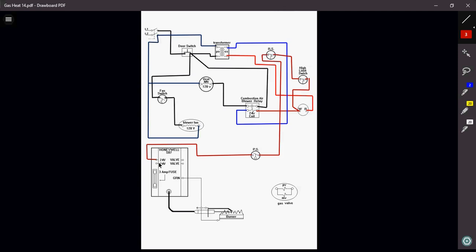Okay? Because where does that call for heat come from? That call for heat comes from the thermostat. My thermostat is right here. So once that switch closes between R and W, I'm going to send my 24-volt signal out to my relay coil, which is going to turn on my vent motor, so that I can now start purging the furnace of any sort of combustible gases that are inside the heat exchanger, if there are any.